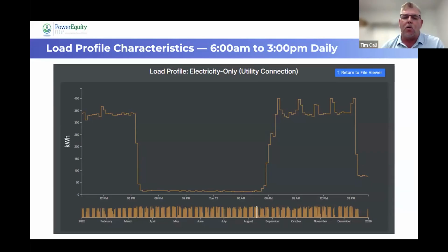So this facility has already modified their behavior for peak and off peak. It also happens to work spectacularly with the option S tariff, because we are avoiding all those big charges, the 38-cent energy during peak, but we get to take advantage of the very, very low demand charges across all time periods. So how does this look when you actually start applying this to the load and the tariff?